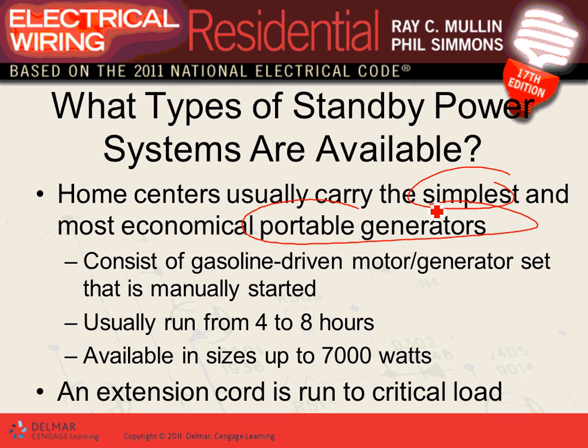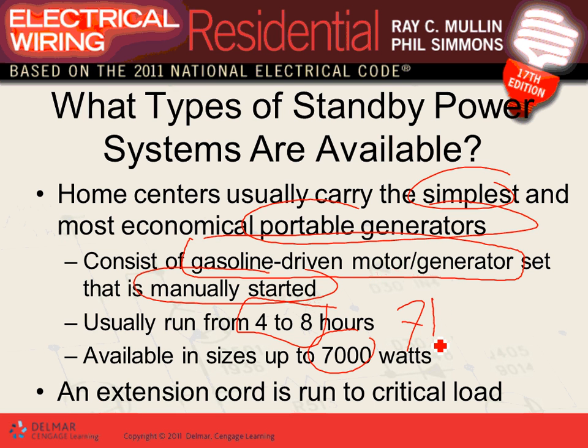The simplest one consists of a gasoline-driven motor generator, that's what they do. It's one set, manually started, you go crank it outside, portable, manually started, gasoline-driven. It can run for a certain number of hours upon the loss of power. You can run your furnace, you can run your refrigerator, your freezer. Sizes, guys, are commonly 5 kW, available in sizes up to 7 kW. So a lot of people have a 2-3 kW generator just to pick up their furnace and their freezers. They come with an extension cord.